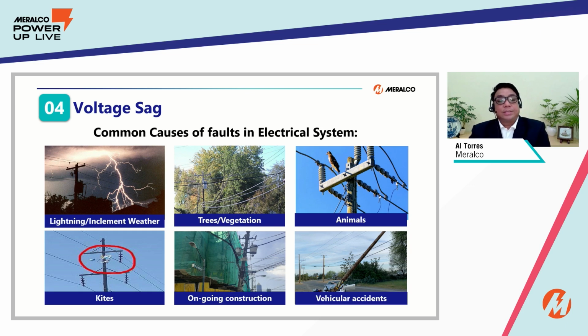So later, Sir Joseph will present the line maintenance activities in order to minimize the occurrence of these disturbances. But please take note, kahit 24/7 i-maintain ni Meralco yung line natin, we can't zero out these disturbances. May lulusot at lulusot pa rin. Kaya nga kami, usually, it takes a two-pronged approach: fortify the line side to minimize the occurrence of disturbances, and at the same time, strengthen the tolerance of your load side equipment, to ensure the continuity of your machine operation. So later on naman, mag-share naman si Sir Hans of MServ regarding the load side solutions for these power quality problems.